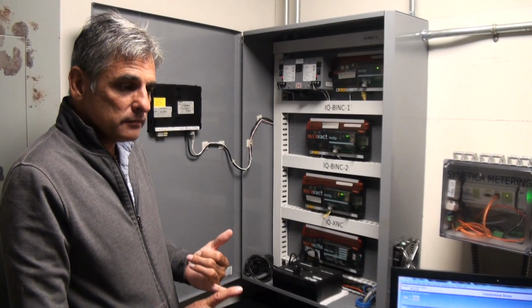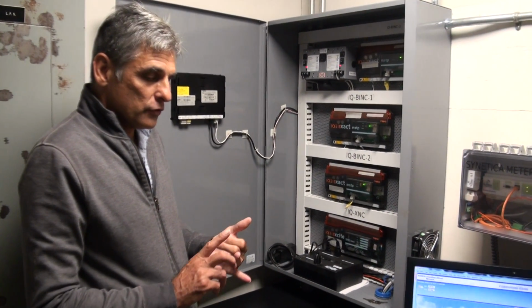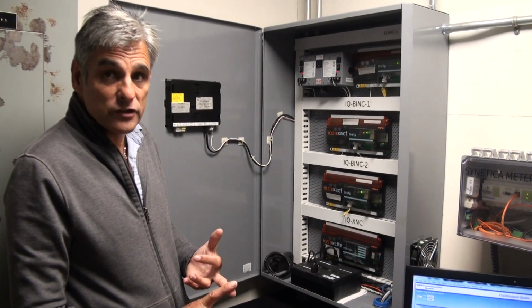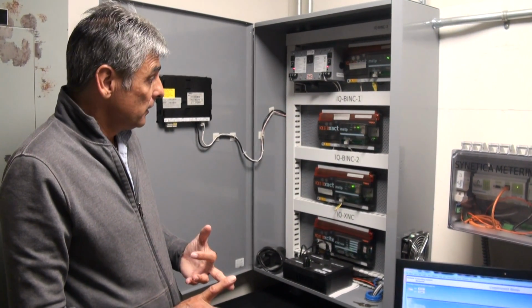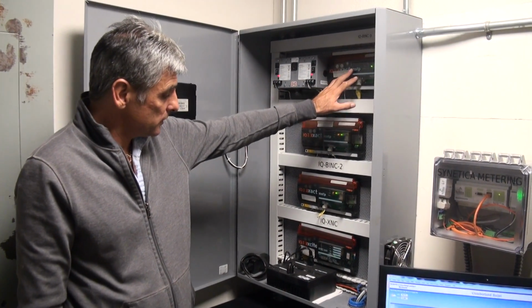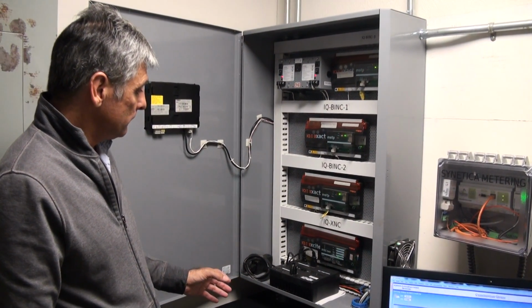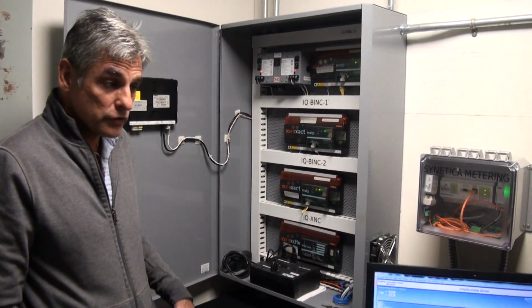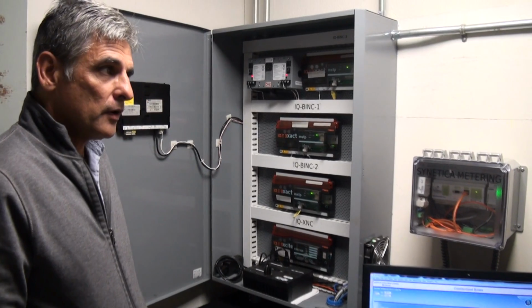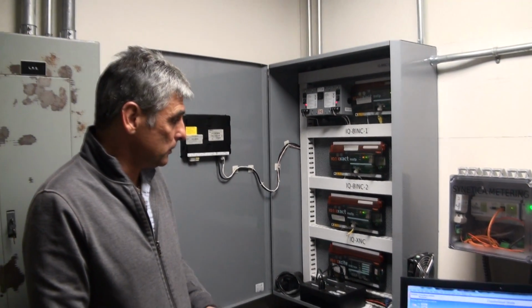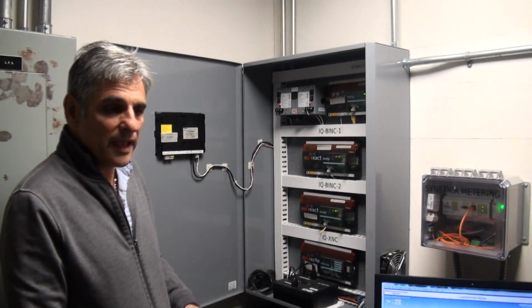So scheduling, control strategy, shutdown strategy in the case of fire, it's all programmed into these 3 units. These 3 units communicate to each floor via a twisted pair cable.